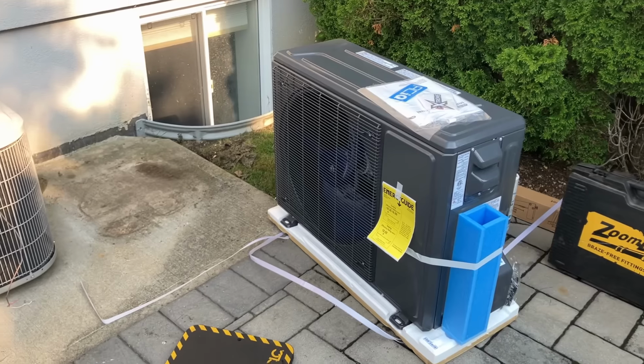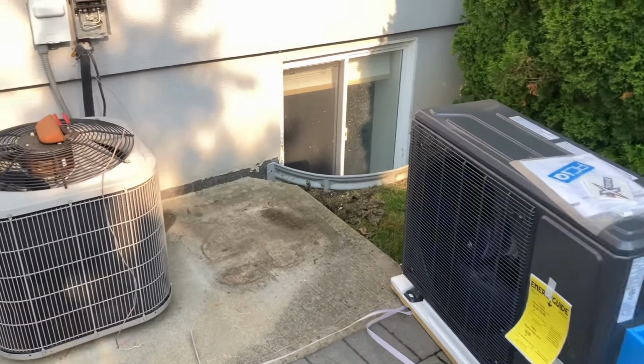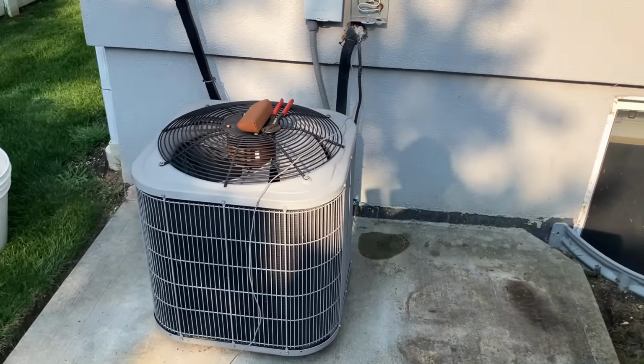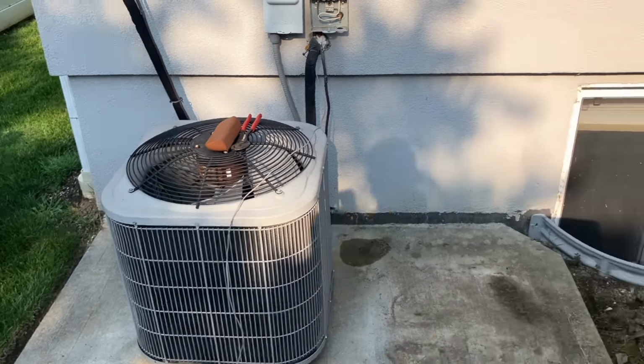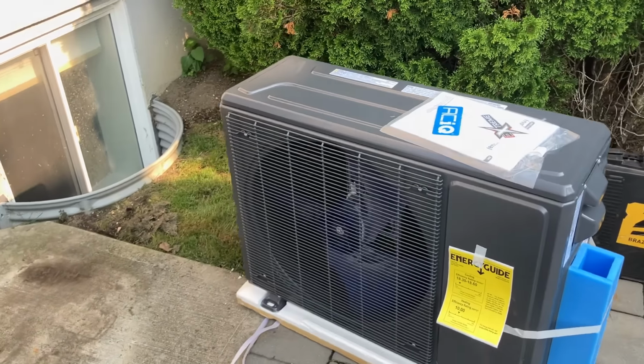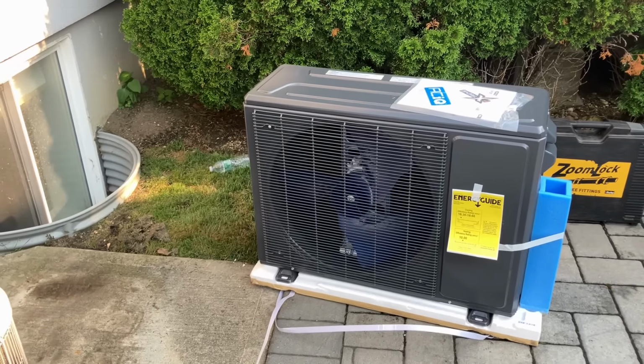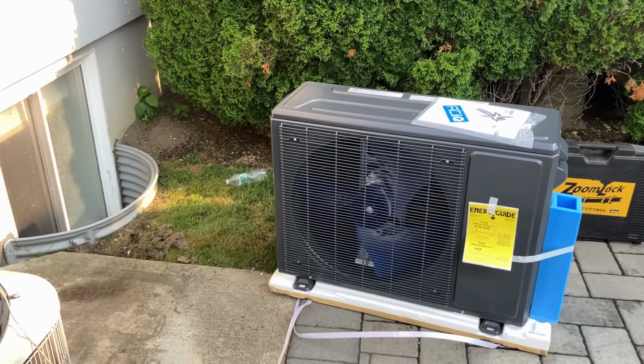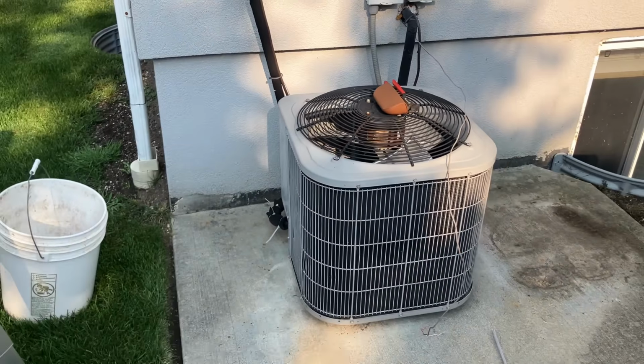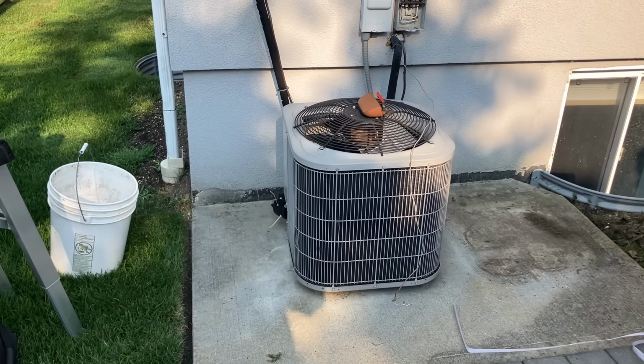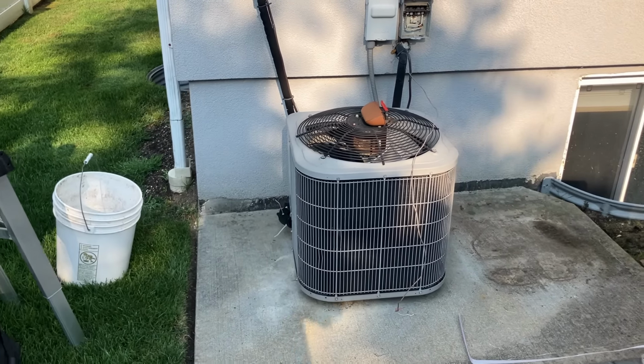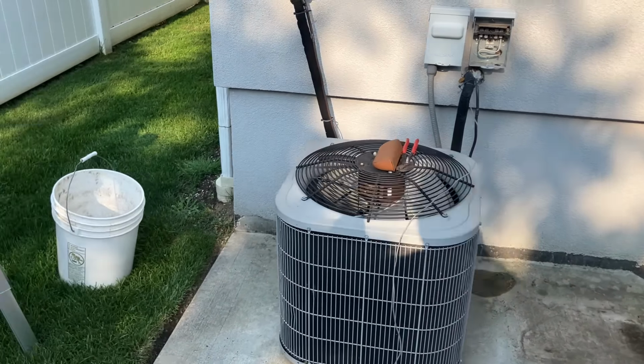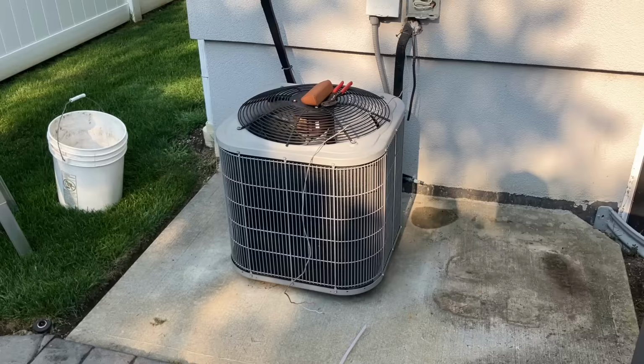Now, before I set this unit into place, I want to explain why we're installing it the way we are. This outdoor unit is going to sit perpendicular to the house, not parallel like this old one. That gives us excellent airflow, outstanding service access, and it also leaves plenty of room for what's coming next. The homeowner plans on replacing the second system next year. God willing, when that happens, we'll install the second side discharge unit facing the opposite direction, leaving a generous working aisle between the 2 systems.